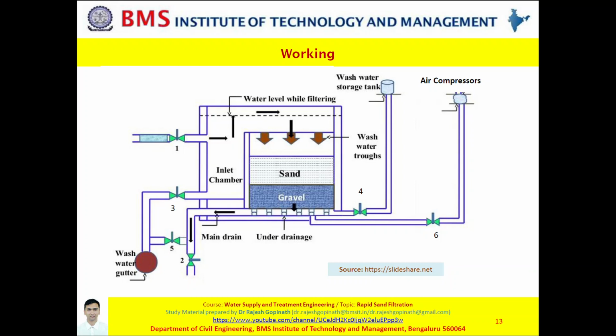Now, when the cleaning operation has to happen, you need to follow a sequence of steps. Step number 1, close the first valve and second valve. Basically, if you remember, during the normal operation, only first and second valve were actually open. The rest were closed. So, when cleaning has to be done, please close V1 and V2.